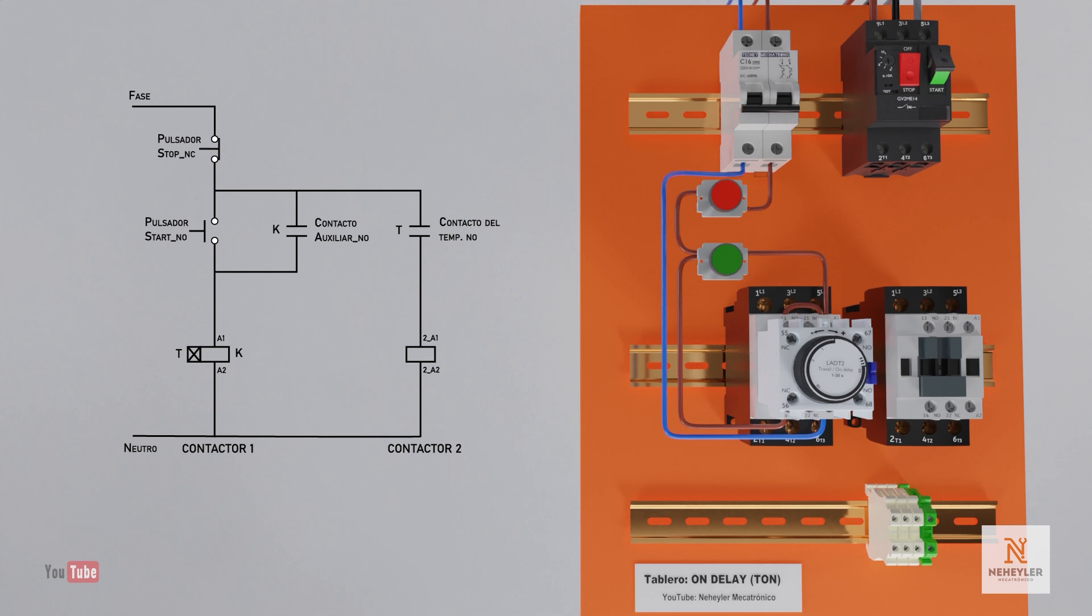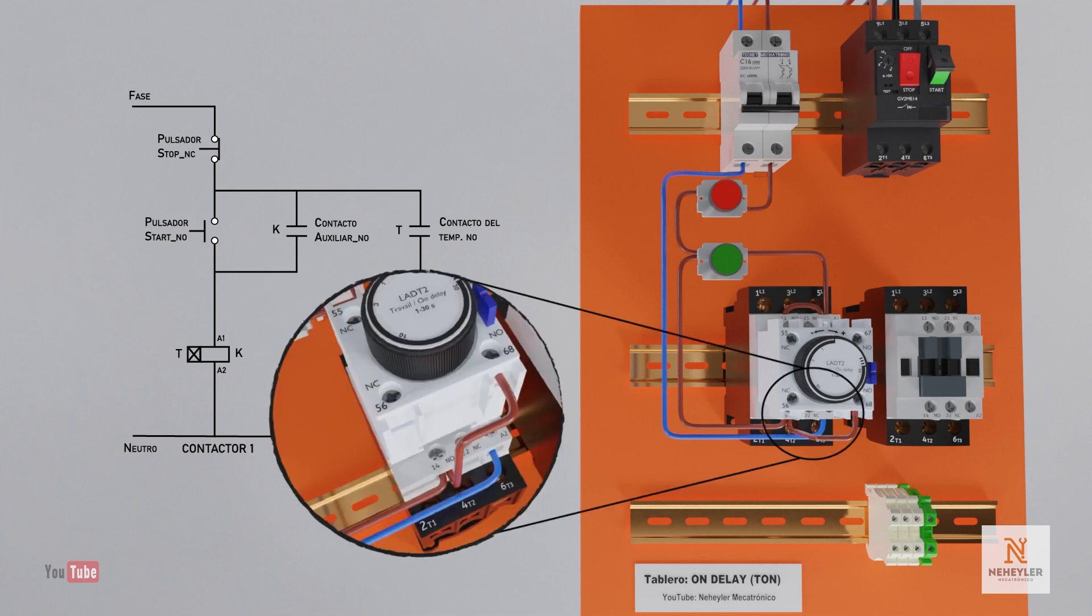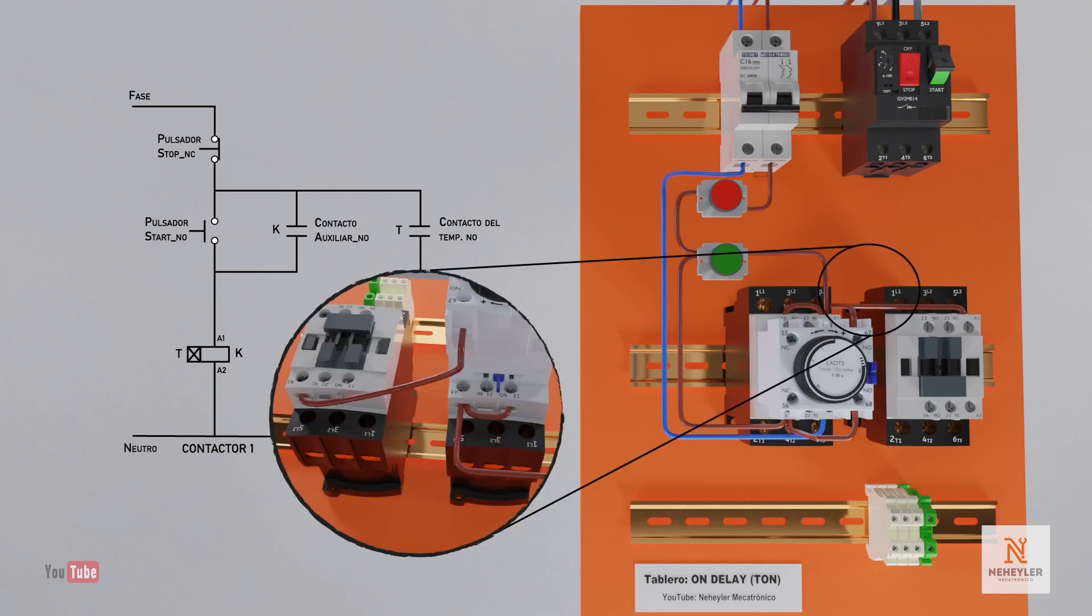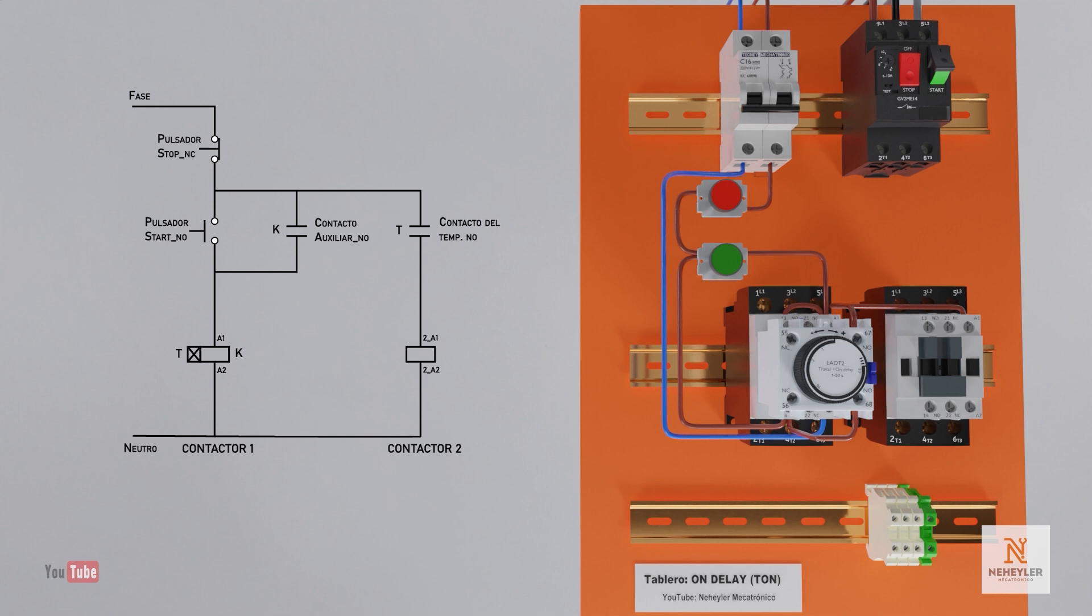From the cable that is connected between the buttons it is connected and led to contacts 67 and 68 of the timer, which is a normally open contact. And later it is taken and connected to terminal A1 of the second contactor coil. We finish the circuit by connecting from terminal A2 of the second contactor to the neutral wire.